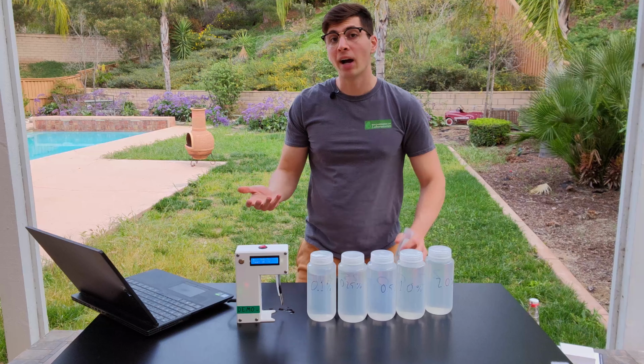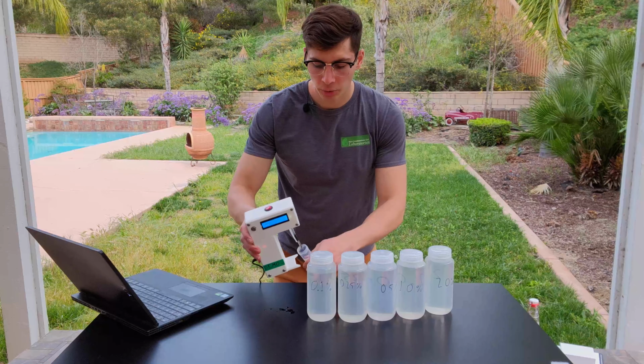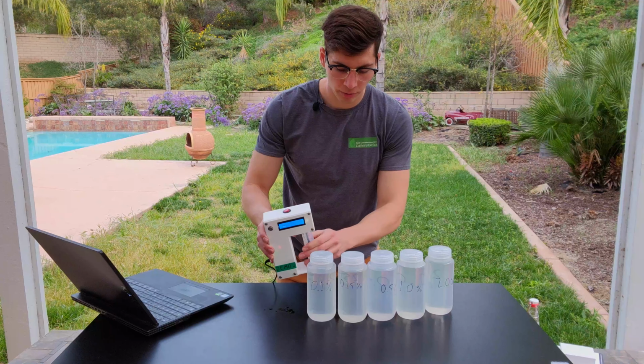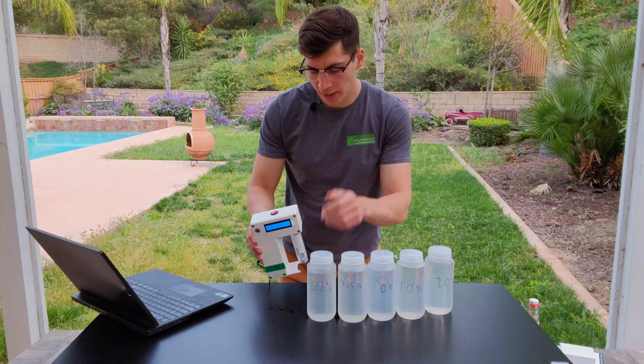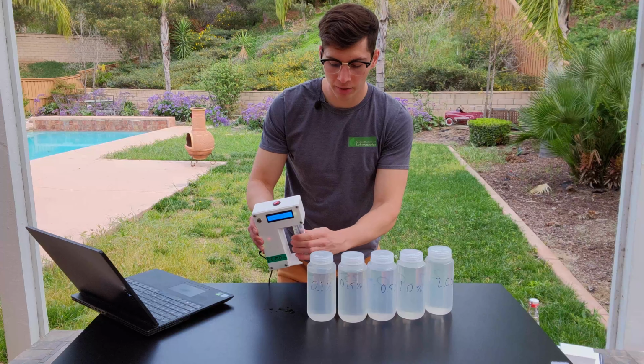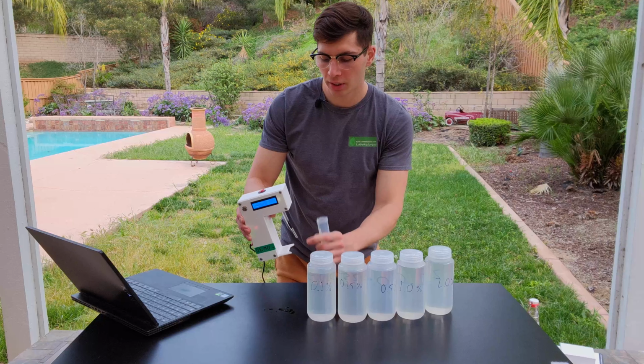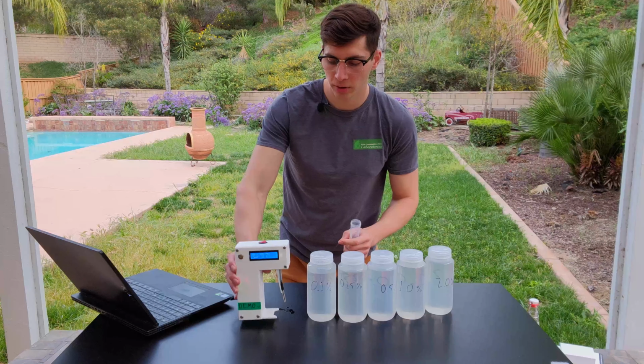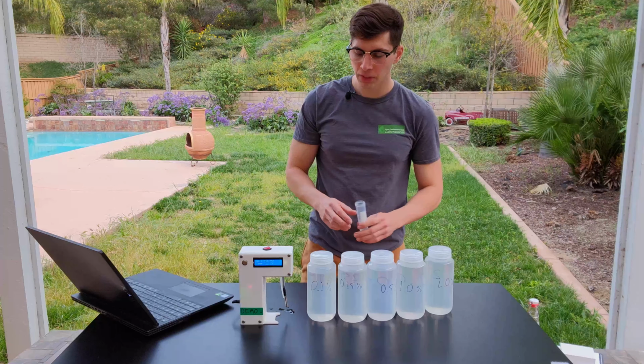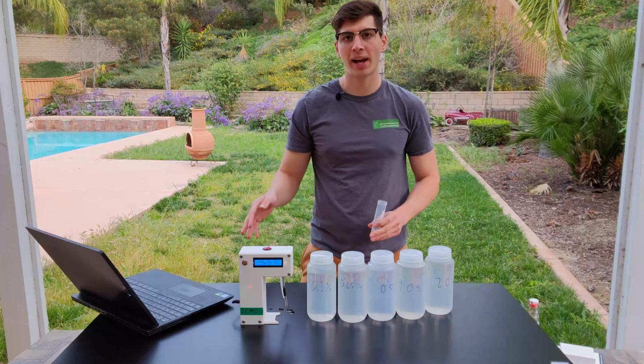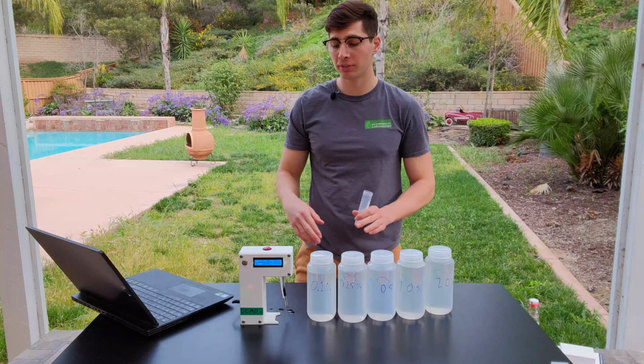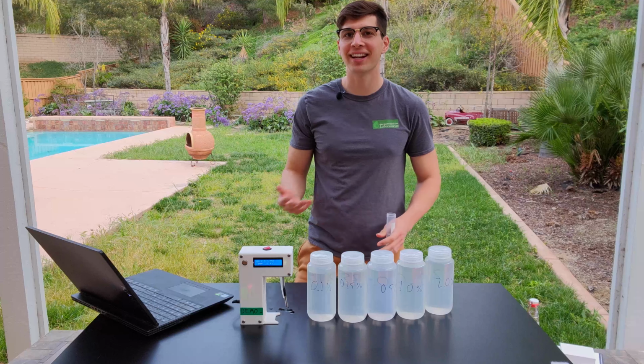Not too bad. Now, when you're done with the device for the day, you can screw in a sample of water just for a second to flush out some of the air in the device and to sort of rinse off the temperature probe and the tube coming out of the detector. And then once the readings settle down pretty low, you can turn it off and store it in a cool, dry place until the next time you want to use it.